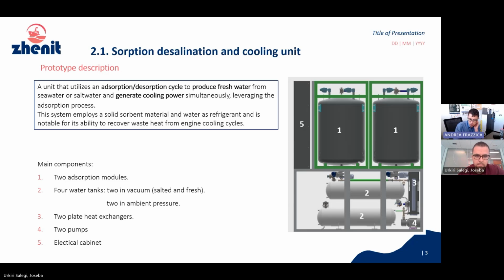Basically, they are trying to integrate all the process inside the reactor, reported here as number 1, these two adsorption modules. We need two adsorption modules because the system works in a batch operation, so when one of these adsorption modules is pressurizing the fluid, the other one is adsorbing, generating cooling capacity. So we need two adsorption modules to have continuous cooling provision.